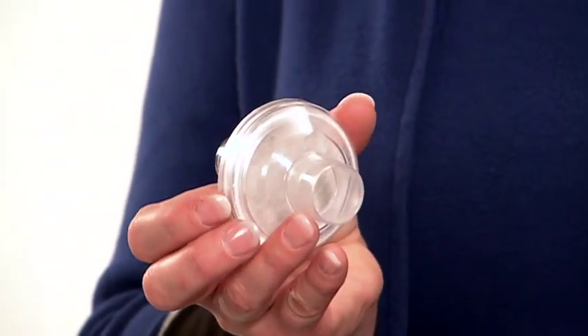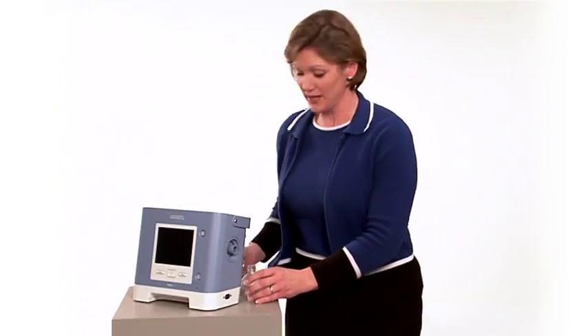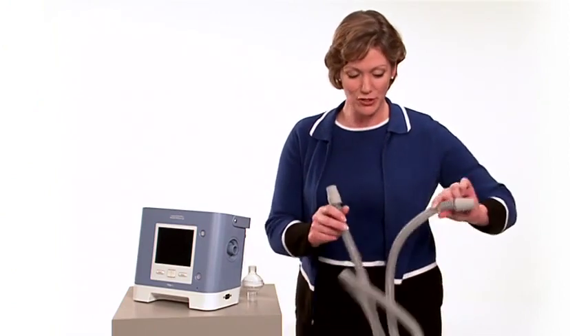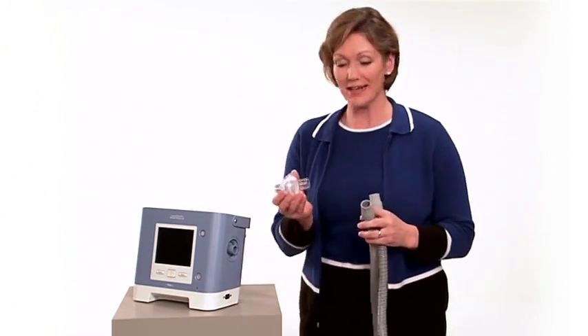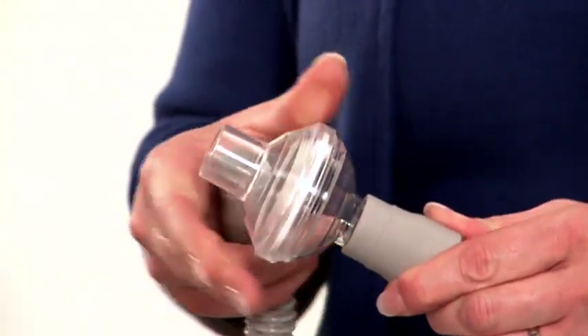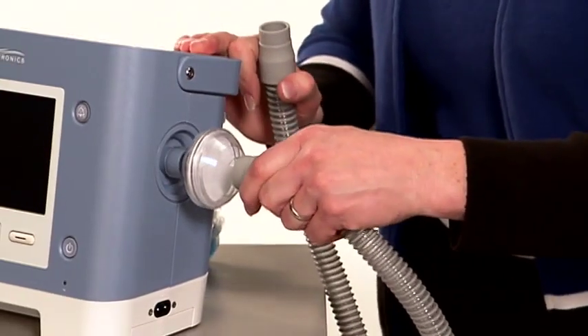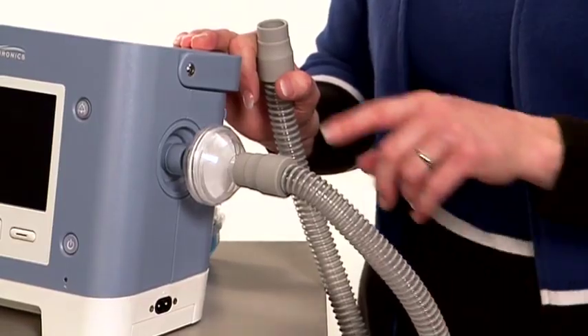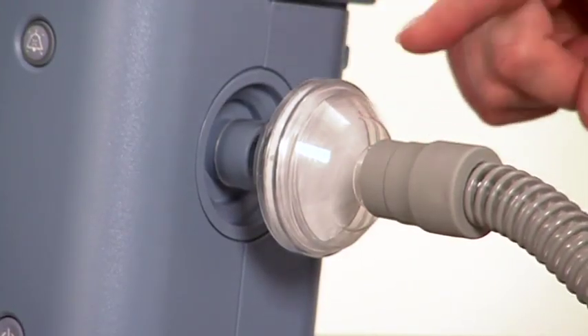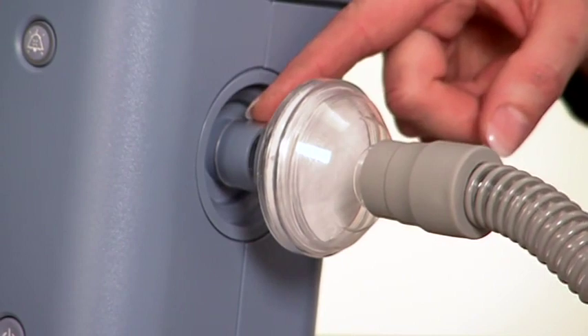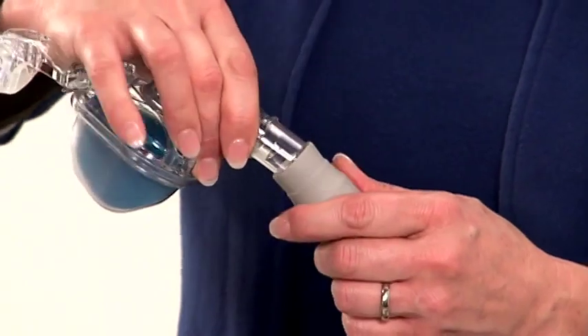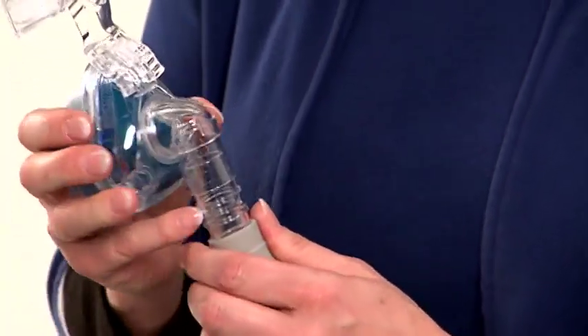The ventilator is designed to work with either a passive exhalation port or an active exhalation valve. An optional bacteria filter can be used with either type of valve. To set a passive circuit up, connect one end of the flexible tubing to the outlet of the optional bacteria filter. Insert the bacteria filter inlet to the breathing circuit connector on the side of the ventilator. If you aren't using the optional bacteria filter, attach the tubing directly to the breathing circuit connector.